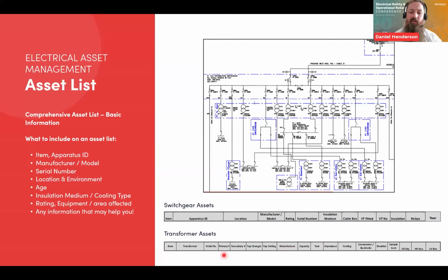And if we're looking at transformers, a lot of the information is going to be the same. It's good to include the primary voltage and the secondary voltage, and what the winding configuration is on the transformer. The tap changer: does it have a tap changer, an on-load tap changer as an example? If it has an on-load tap changer, record the make, manufacturer, model, and any key considerations with that. If it's an offload tap changer, is it lockable? Is it locked to prevent operation on load? Does it have the necessary signage on it? All safety related information that's good to keep in one place.